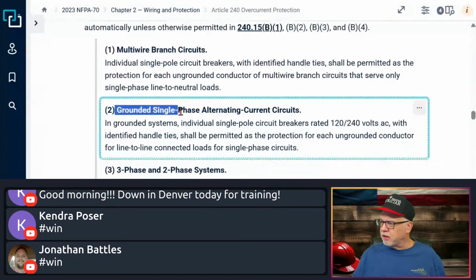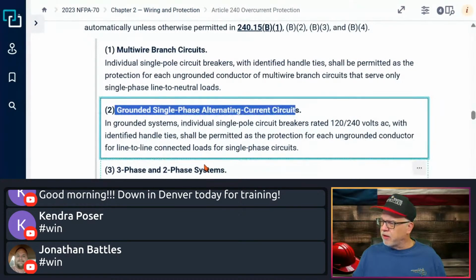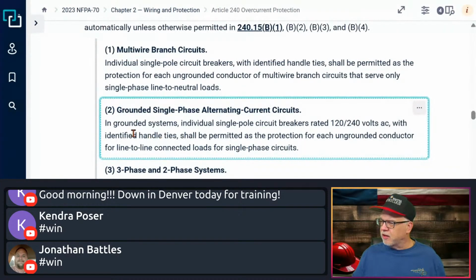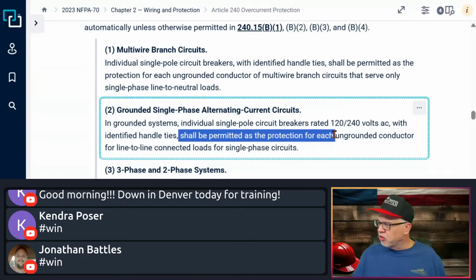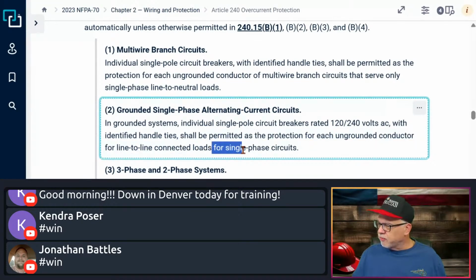Again, this is just talking about grounded single phase alternating currents. It says in a grounded system, individual single pole circuit breakers rated 120/240 volt AC with identified handle ties, you have that again, shall be permitted as the protection of each ungrounded conductor in a line-to-line connected load for single phase loads.